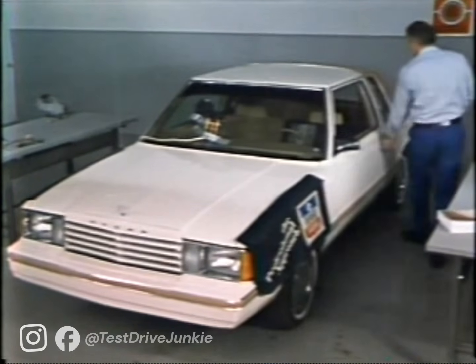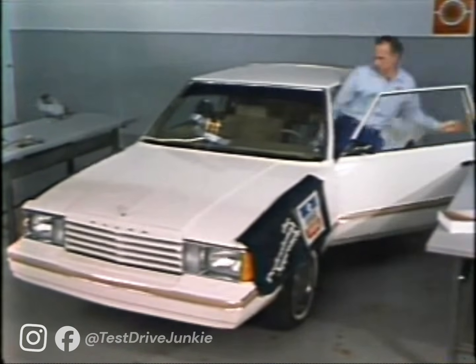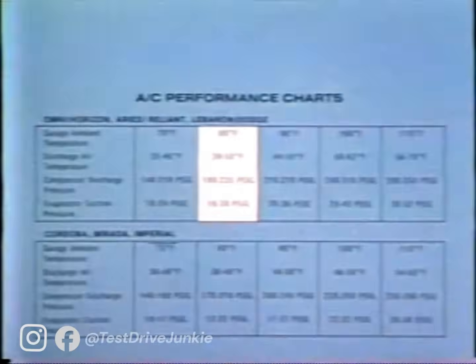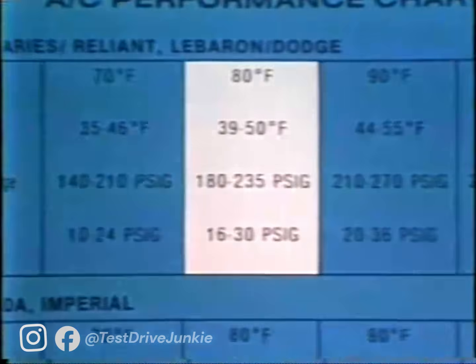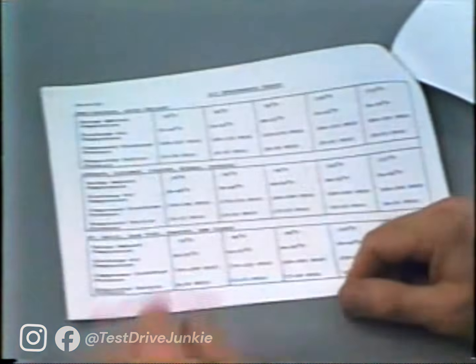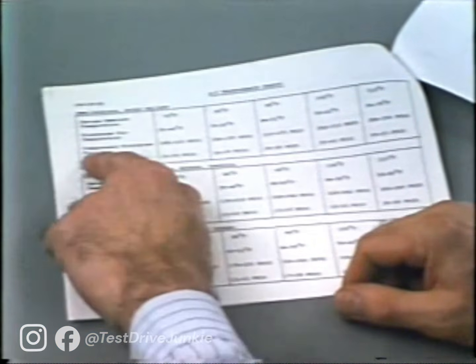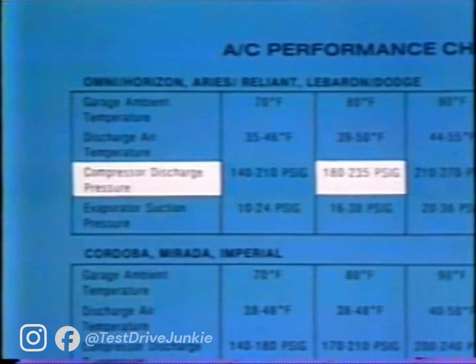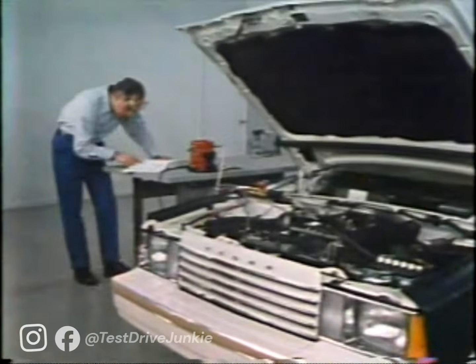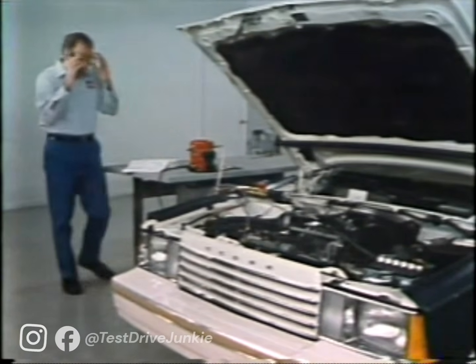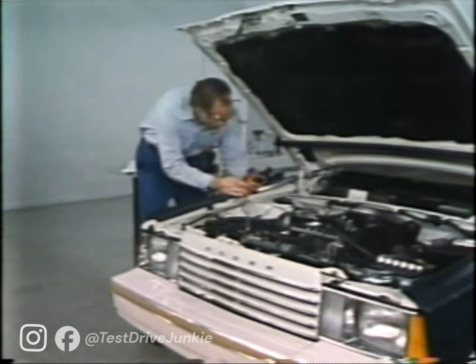To make sure, we can check our gauge readings and discharge temperature against the values in the appropriate ambient temperature column of the AC performance chart. In this case, the discharge pressure reading is too high. This flow chart in the service manual will help you determine the cause of any variant gauge readings. If you have to evacuate and charge the system, follow the procedures in the service manual.